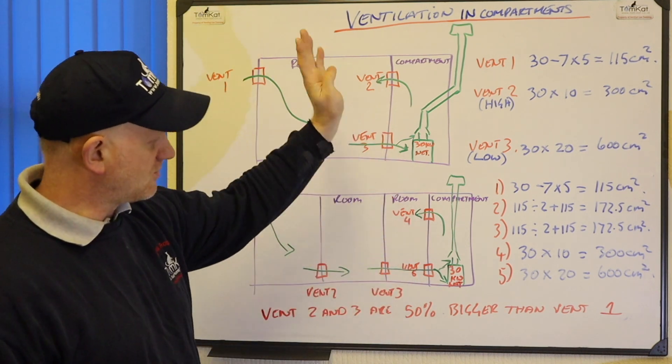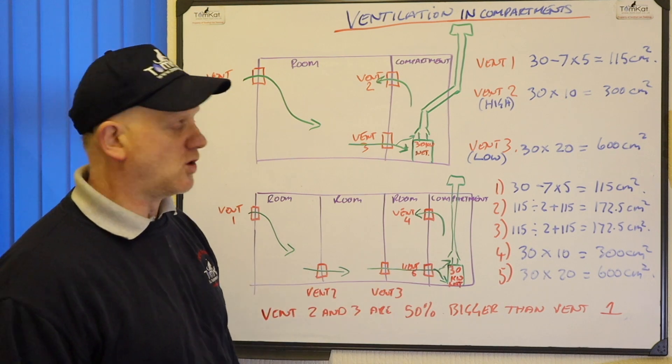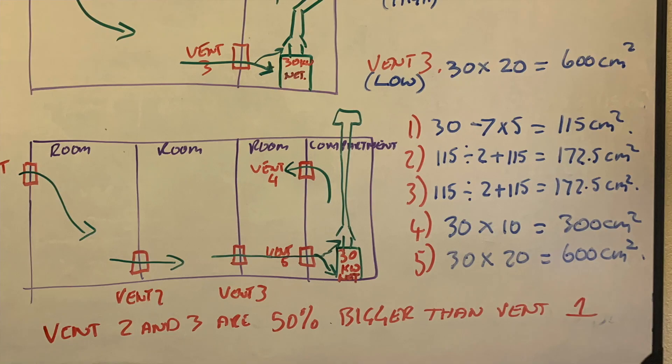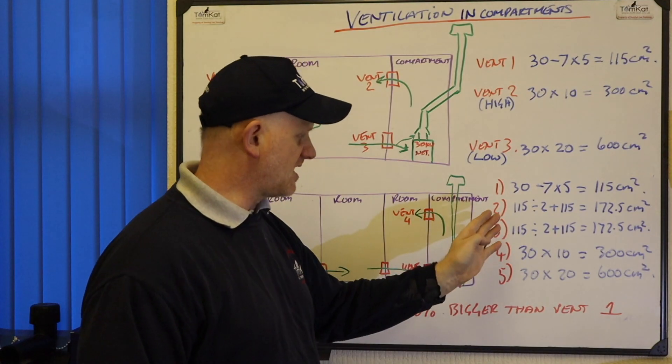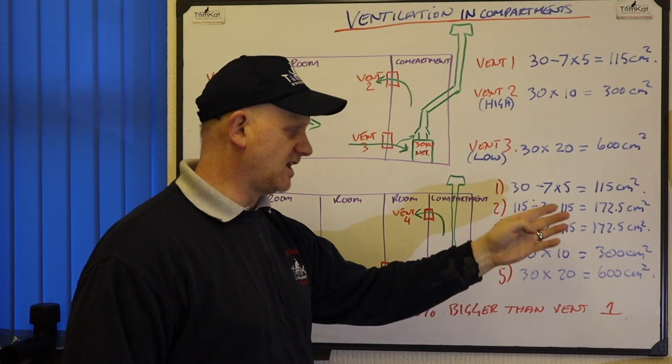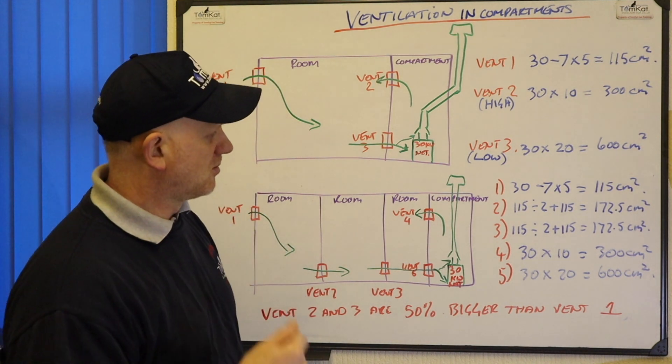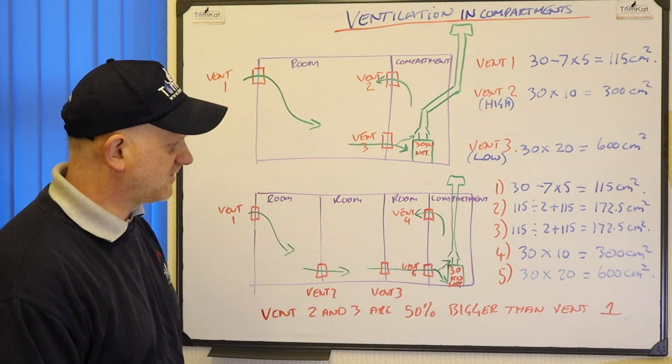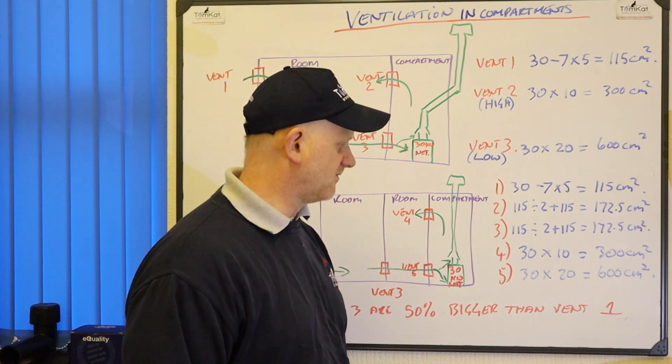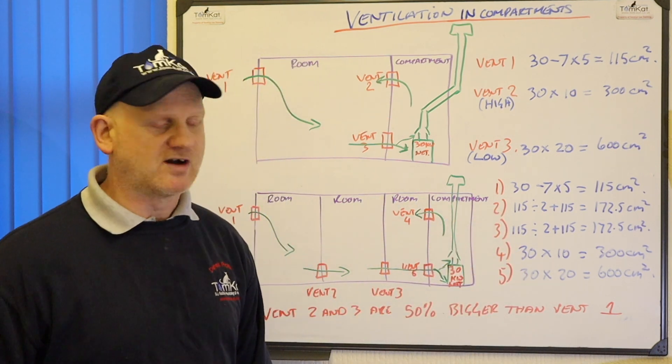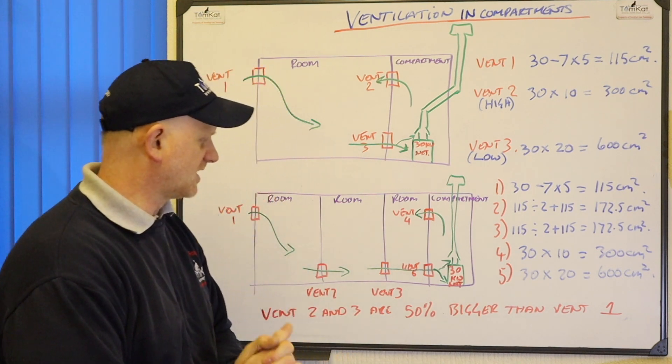So again if we look at this scenario it's the same boiler, it's a 30kW net. Vent number 1 which is the outside vent again will be 30 minus 7 times 5 is 115. Vents 2 and 3, as we say here, need to be 50% bigger than vent 1. So it's 115 divided by 2 plus the 115 is 172.5. Vent 3 is the same, 115 divided by 2 plus 115 is 172.5. So like we did in the first video of ventilation.